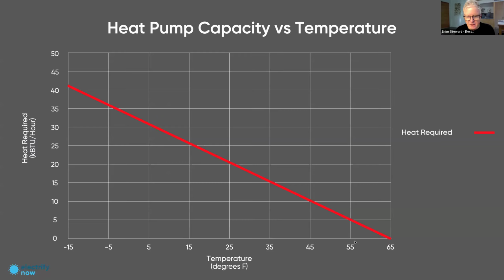So that's what this line represents: the colder it is, the more energy you need. You can then plot how any given heat pump performs, and each of these lines will differ depending on the capability of the exact equipment specified. In general, older style, standard heat pumps can provide a lot of heat when you don't need it, but provide less heat when it gets really cold.